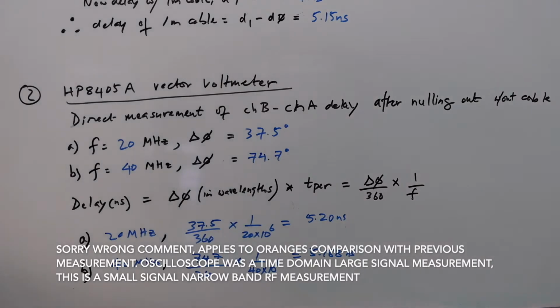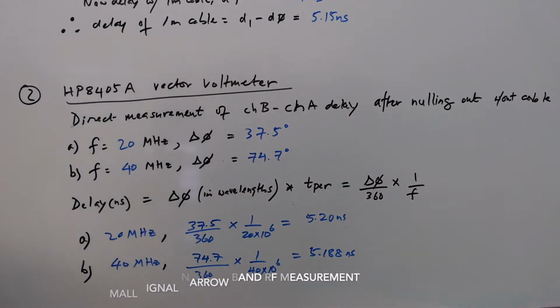Of course, these are sinusoidal signals, so these are narrow band measurements, tuned for that particular frequency, so any inaccuracies or harmonics or those types of effects are not in the measurement. The oscilloscope measurement of course requires sharp edges, which means you have a lot of high frequency components in the edges of those signals, so we need a good oscilloscope with high bandwidth to measure these sharp rise times to get a good delay number. But here, this being an RF instrument, it uses a pure single first harmonic of the signal, which is the two frequencies we used here.